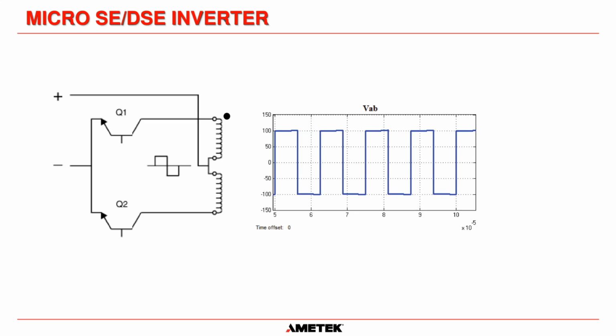The challenge is doing it in a way, because remember, this is 60 times a second we are switching these IGBTs, and that is every second of every hour of every day of every year. And you know, the minimum expectation lifespan of our UPS is 20 years. So there's a lot of switching going on, and we need to make sure that that happens correctly every time. So that's where the software and the design comes in. But once again, the theory, the principle behind it is very, very simple.